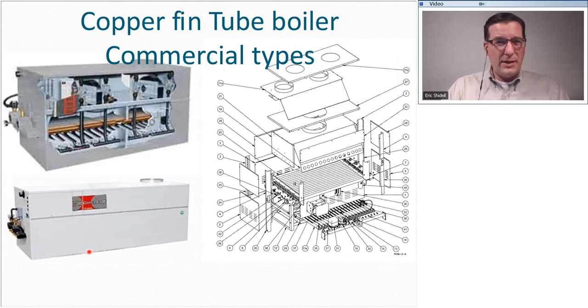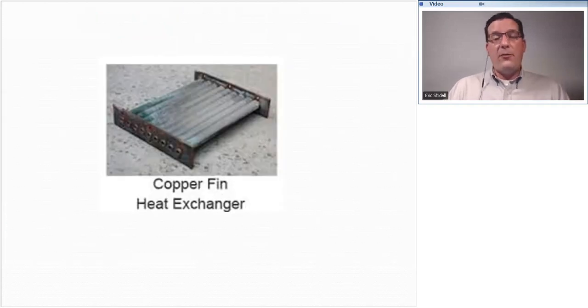Copper fin tube boilers get up in size to, I think they top out right around 2.7 million BTU input. Here again, entering and leaving at the same plane. And that heat exchanger is just pretty long. Lots of burners underneath it. There's the heat exchanger in the middle. Here's a cutaway from, I think this is an RBI. There's a heat exchanger with all the burners underneath it. The copper fin tube boiler gets its name from that heat exchanger, which is really a copper tube with copper fins on the tube, and a bunch of them. This is the heat exchanger right here. That's it. You can't get a whole lot more simple than that. It is a copper fin tube boiler.